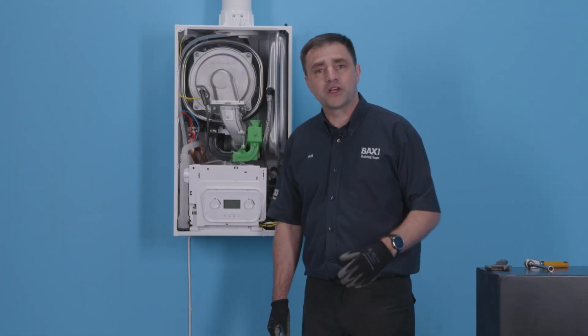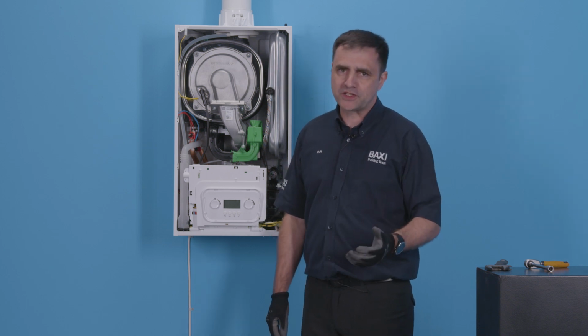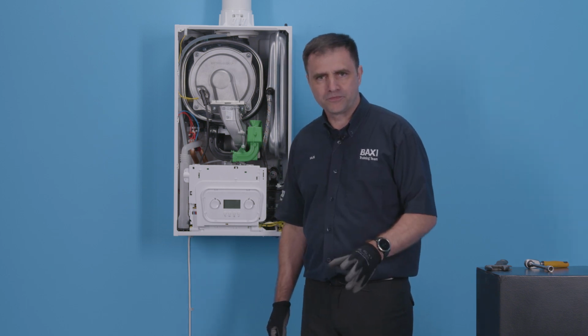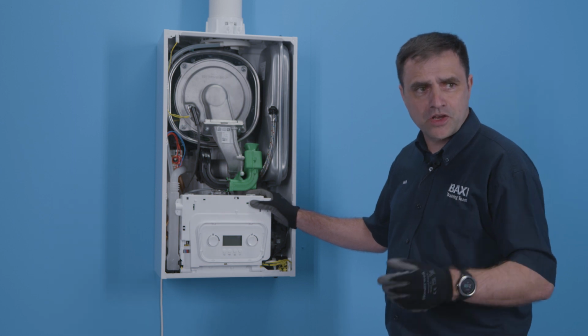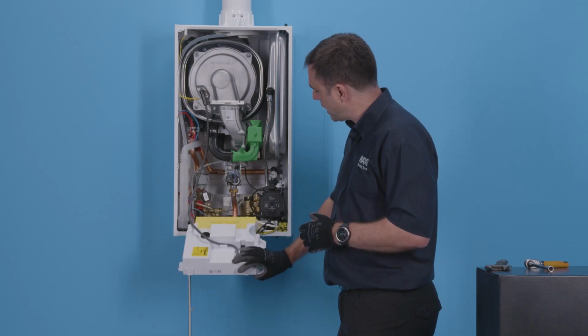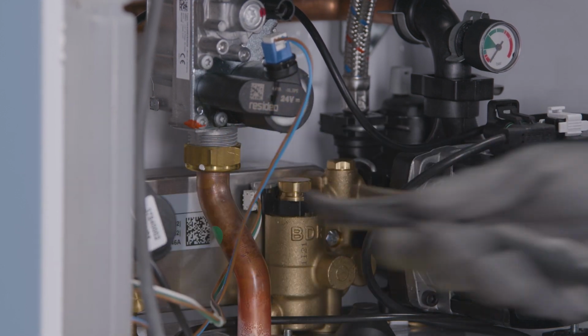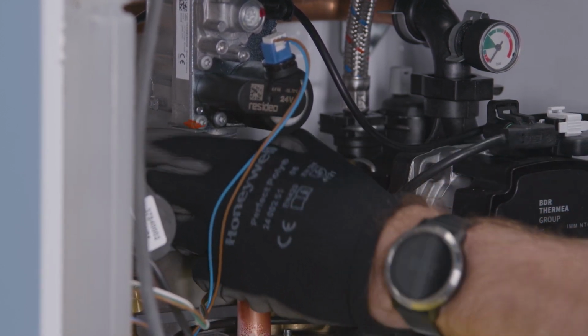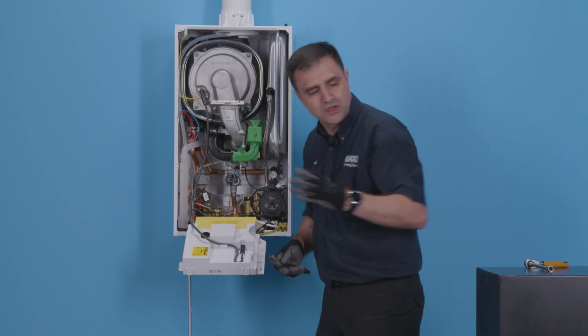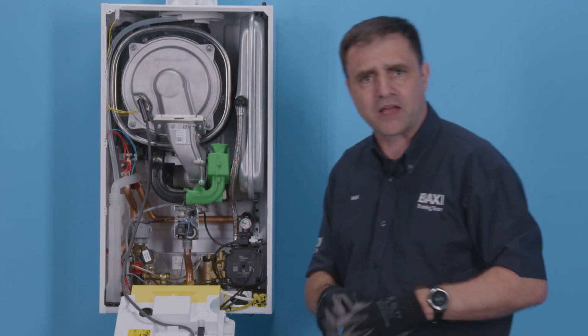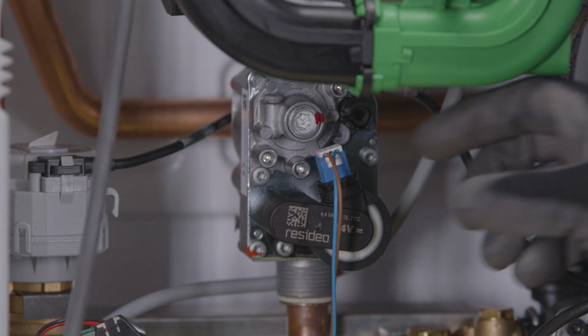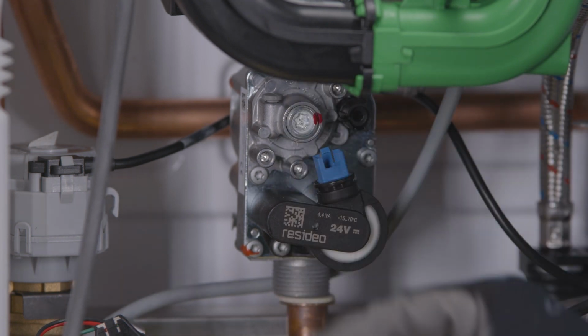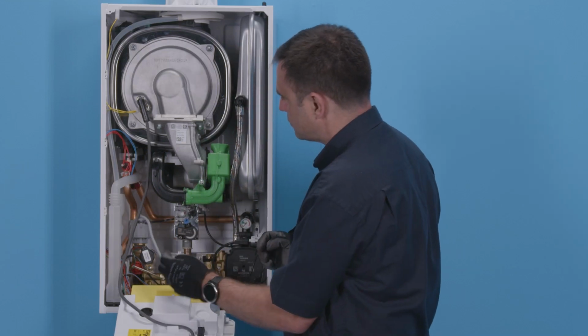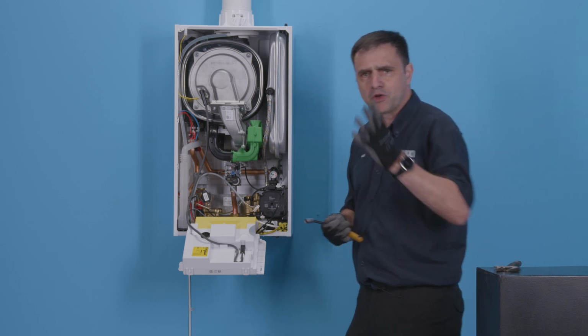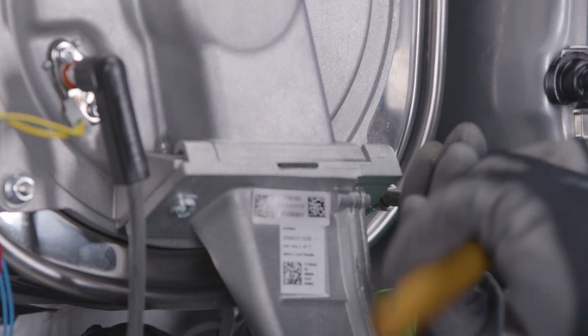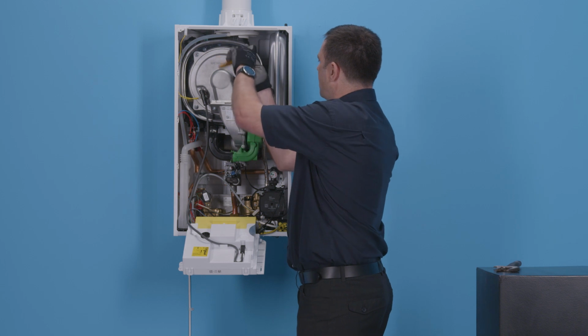So now, what I'm going to do is run you through a full service. What to take apart and what to look for. Make sure that the gas and electricity is isolated. Pull the front flap down, undo the union for the gas. Now that's just a 3/4 standard washer, so there's no worry about having to replace that. You'll be carrying that in your toolkit. Then remove the wires to the gas valve and to the fan. Once I've done that, get a 10mm socket or spanner, undo the connections around the burner plate.